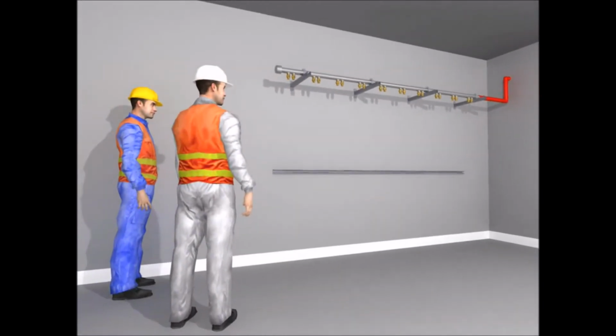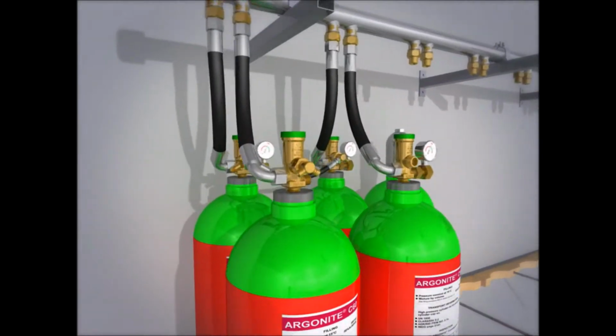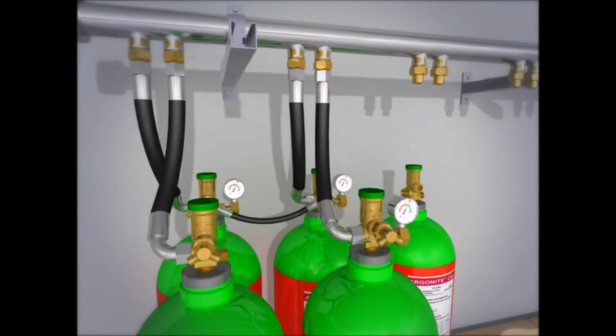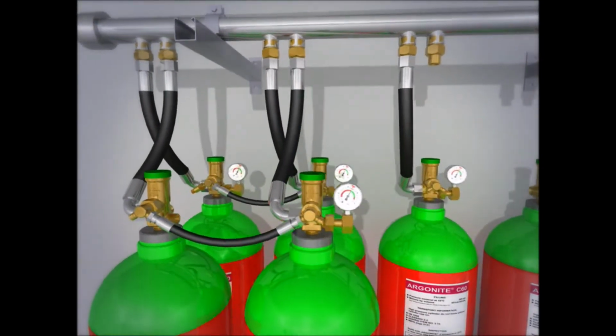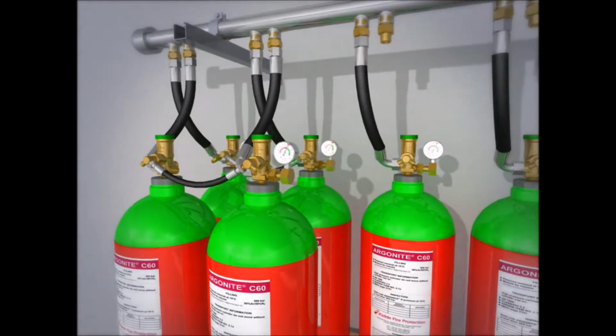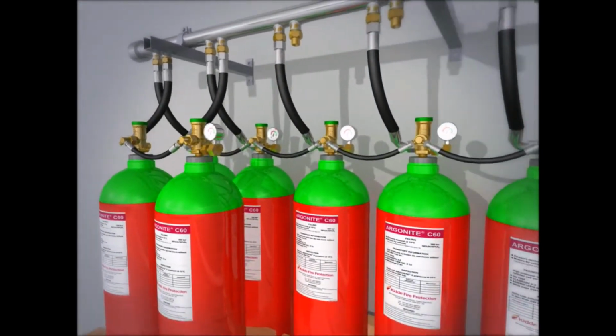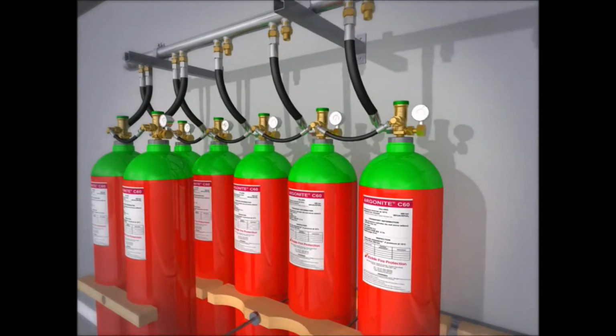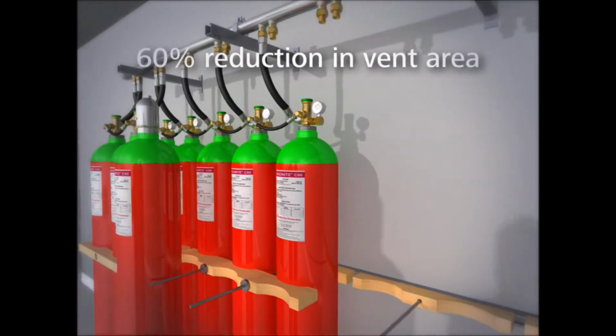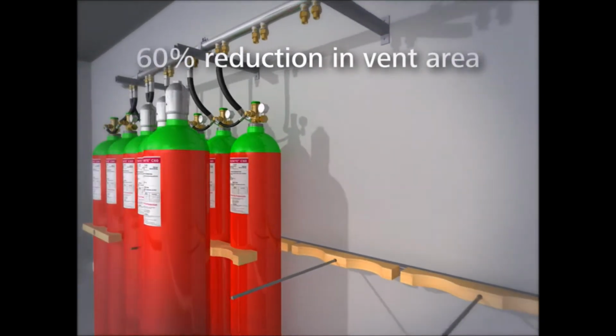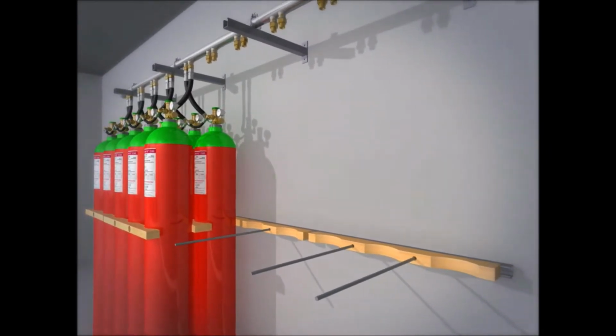The Kidde team have listened, and the Argonite C60 flow control technology makes possible a dramatic 60% reduction in peak mass flow. And that means a substantially reduced pressure impulse or a much lower vent area demand in the protected space.